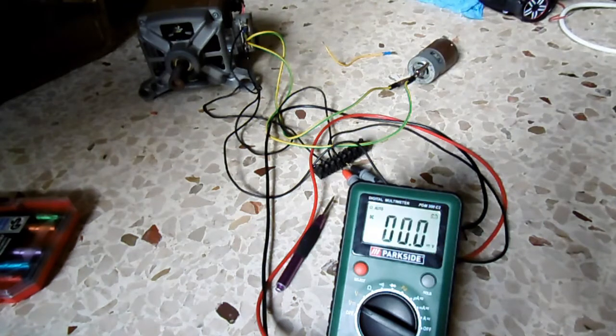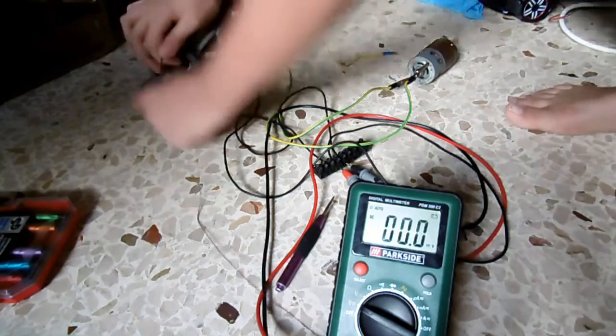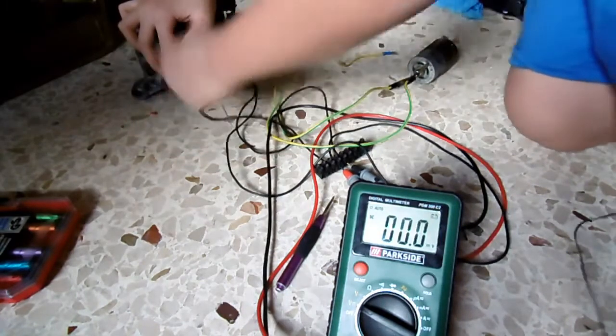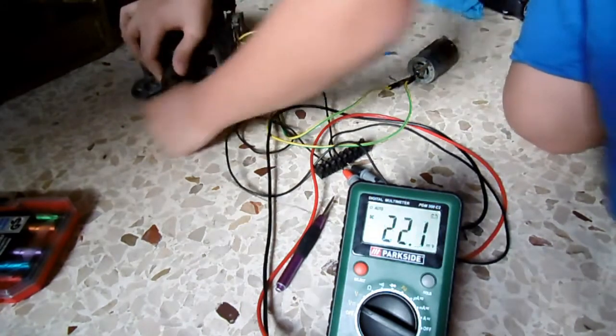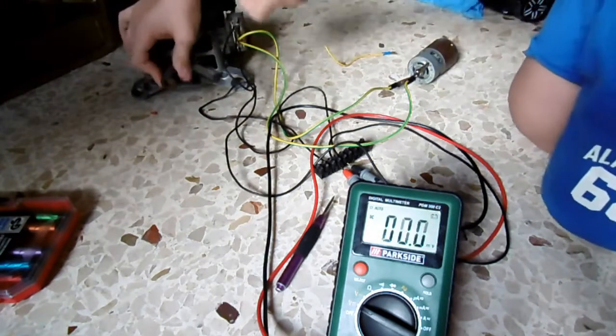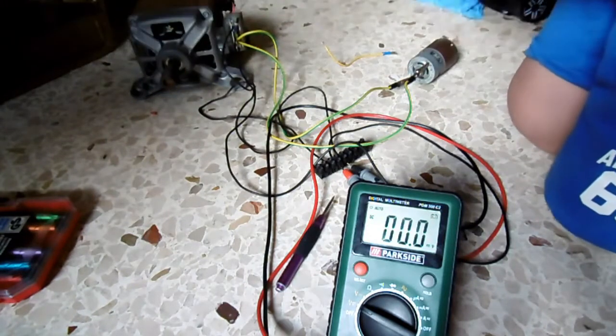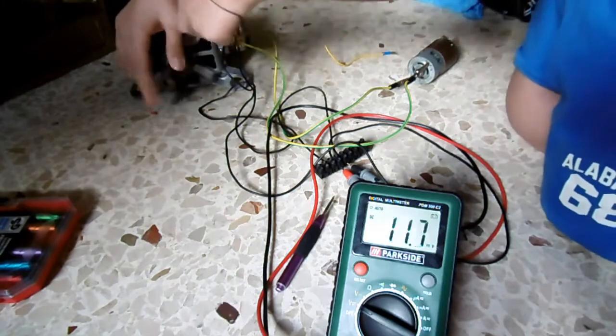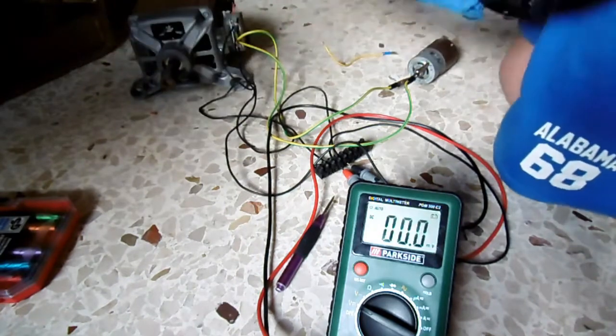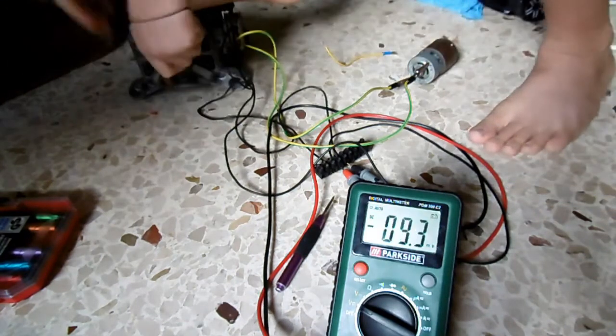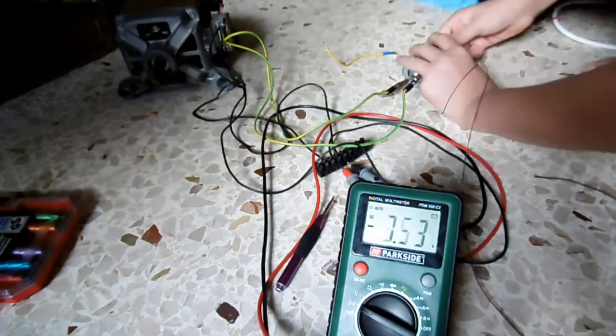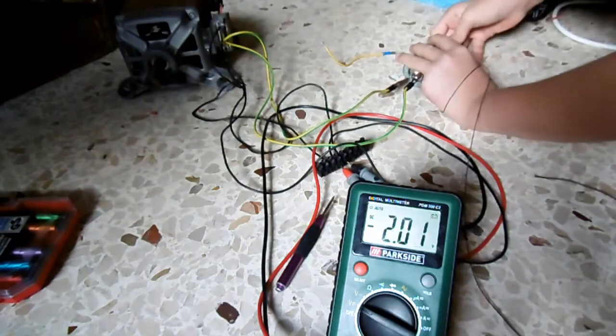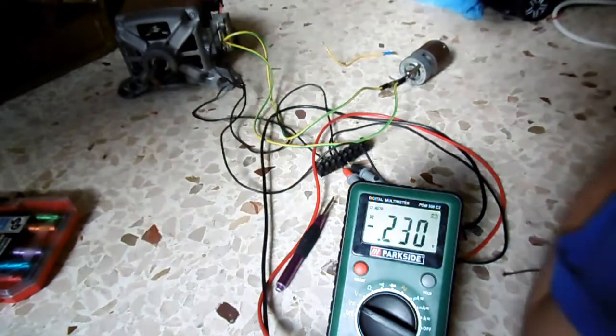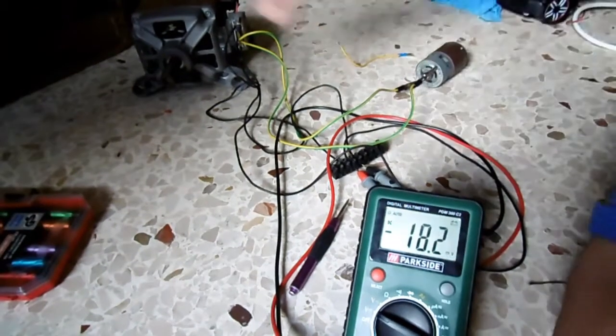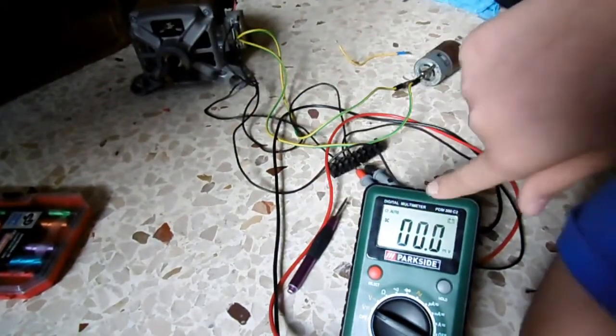That was with no excitation. Now watch the multimeter screen once I turn the small DC generator which powers the field winding at low speed. The voltage should be low, but much higher than before. At low speeds, when I turn the small electric motor to excite the field winding, I get about 4 volts, which is pretty good.